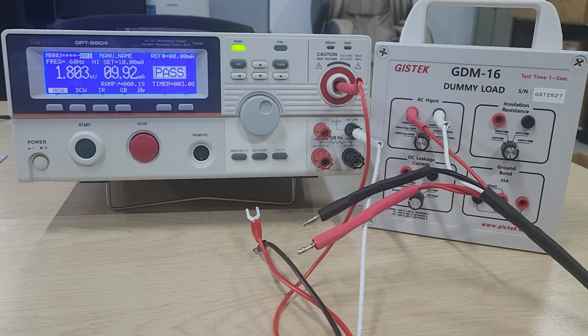The test result may vary depending on the resistance value error of the dummy load, the output error of the AC withstanding voltage tester, and measurement error, but the error may typically be around 0.05 milliampere.